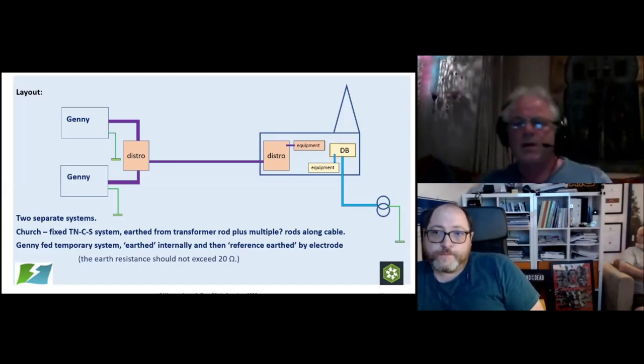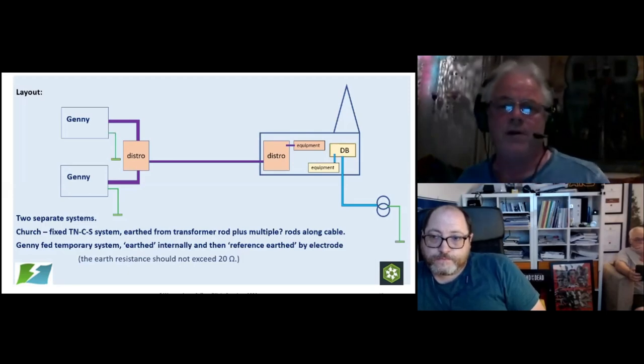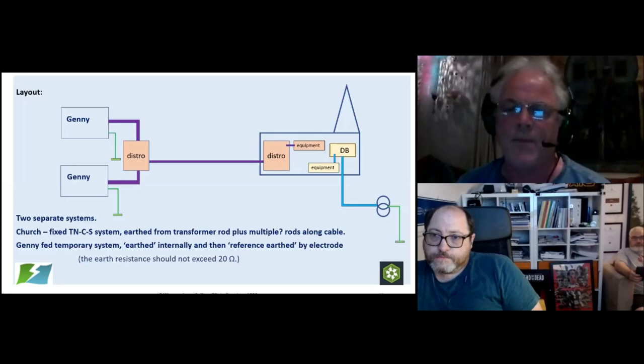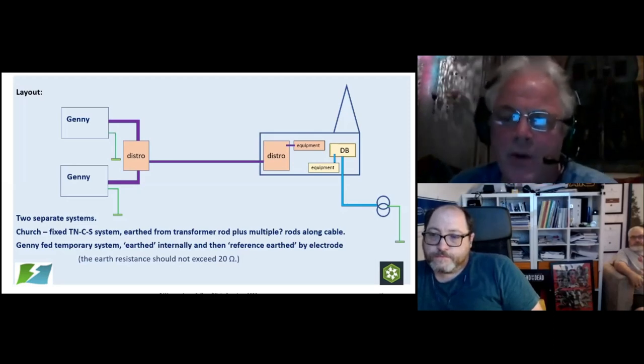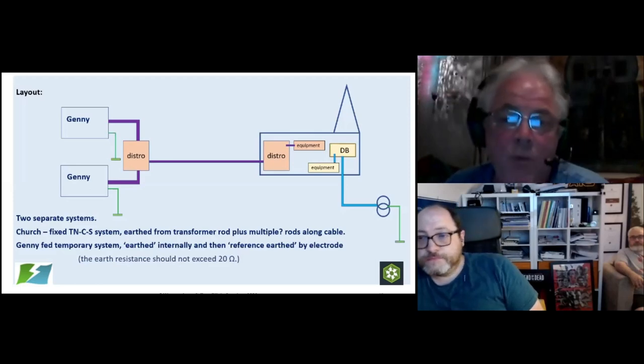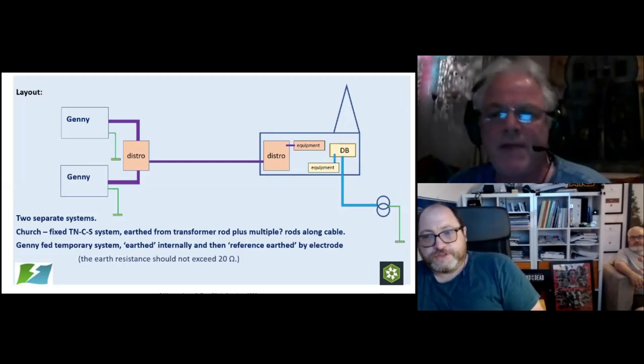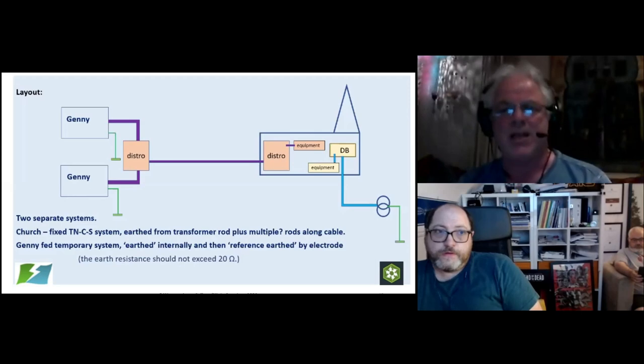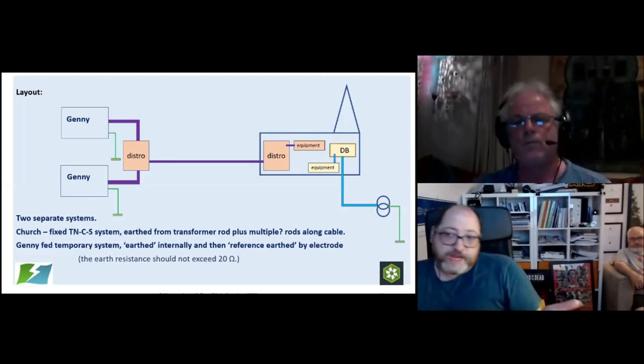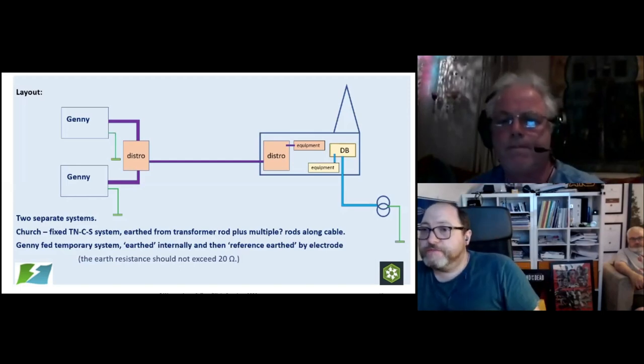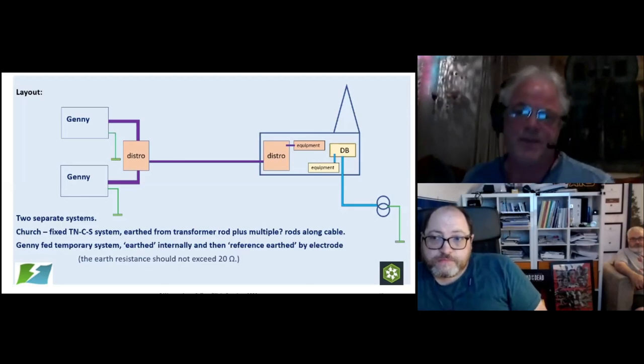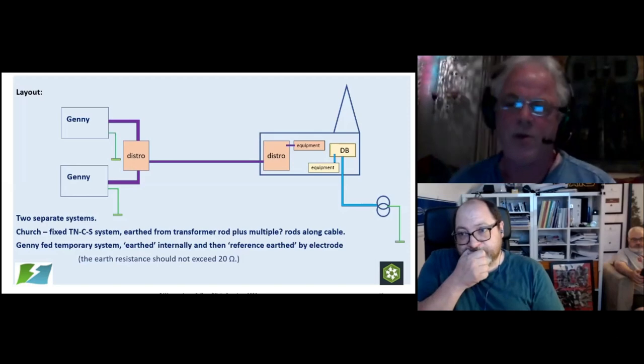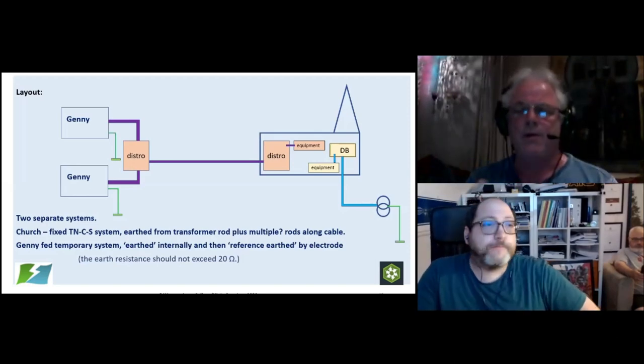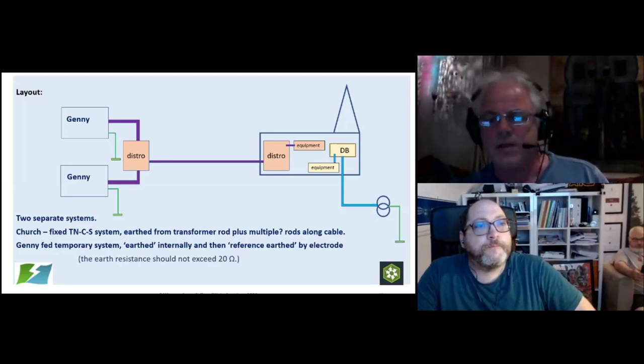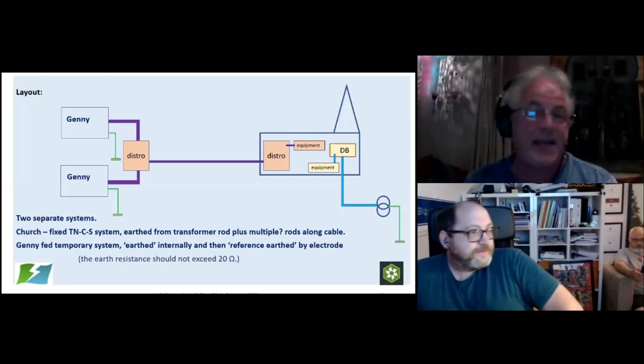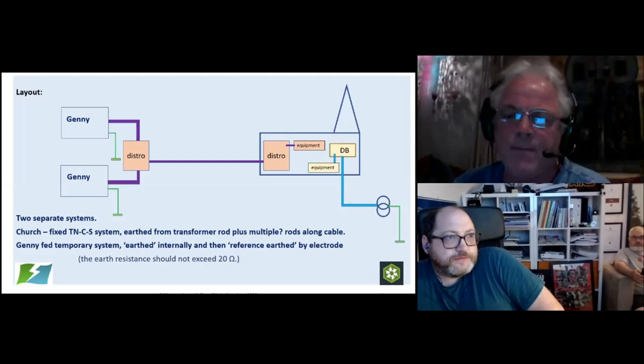So your distribution cables, you can't just throw them anywhere. We had a situation on a site some years ago where somebody had run a cable up a gantry and through a doorway, and it was a metal door, and the wind caught the door and it sliced the cable in half. And that wasn't protected by an RCD. So there is always that risk, but the reason it happened is because the cable was run where it shouldn't be. So if a cable doesn't have instantaneous disconnection, risk is mitigated with suitable selection and erection, otherwise it's just not installed. Most distribution circuits are protected by a selectable RCD with a time delay. It's not a requirement. You can have distribution circuits which have no RCD protection, but always make sure the cable is run where it is at least out of the risk of any damage, and protect it. So we mitigate the risk that way.